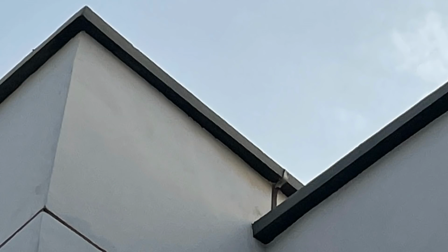So from the air termination rod, you also have what we call down conductors. The down conductors are also the same type of tapes, PVC covered copper tapes, 25 by 3 mil. They come down along your building, vertically down. Again, I'm showing you some examples from where we live right now. You can see those down conductors, those copper tapes that run vertically down your building.